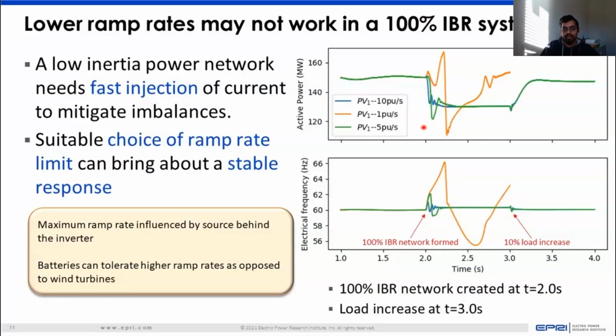And rather it's the 10 per unit per second, and here even 5 per unit per second provides a reasonable response, or provides a good settling point, a good steady state frequency, and for the subsequent load increase that happens in the 100% IBR network, it's able to even tolerate that and provide a satisfactory response. So I want to lay very crucial emphasis on the fact that what might seem a good ramp rate from a strong network perspective might actually not be a good ramp rate as the system strength decreases and as you want these inverter-based resources to provide faster response.